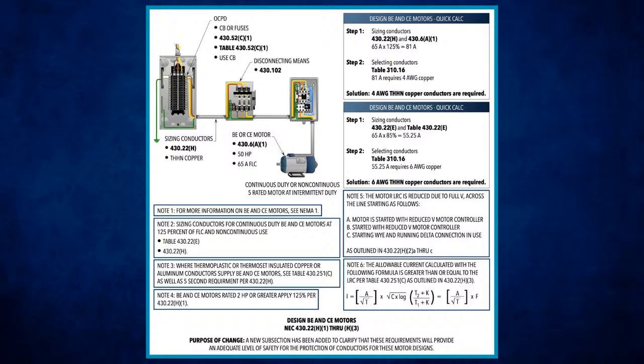That'll be a number 6 conductor. Now, if I go over and look at 240.6A, which is now going to take you to table 240.6A, and I go down and look at the next size above that, the overcurrent protection device is a 60 amp. But yet I can protect based on the load, or I can protect what? The conductor. True. Now if the conductor's at 65 amps, I can look at that table again, 240.6A, and it tells me the next size above that is a 70 amp.